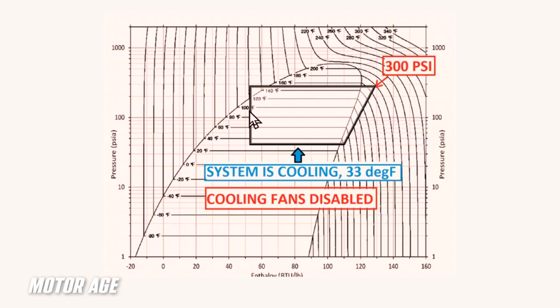And pressure drop across the restriction is good, bringing our temperature to, again, around 33 degrees Fahrenheit entering the evaporator. And we have good heat absorption here across the evaporator. So is this system working? Absolutely. The system's working. And the customer at this point probably doesn't even really have a complaint because there's no detectable loss in performance. But this refrigerant loop enthalpy chart shows us that this system is working very hard to achieve desirable results.